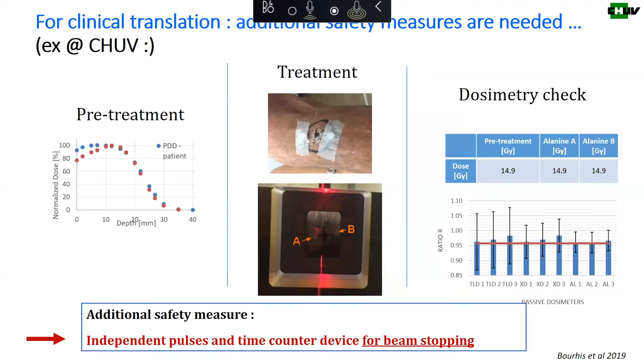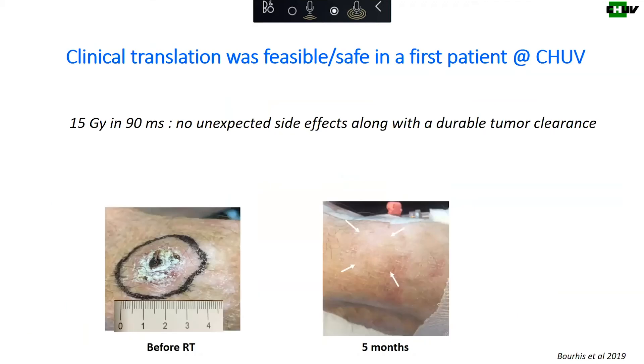For clinical translation, there may be additional safety measures needed, because it goes so fast that you want to stop the beam exactly after the number of pulses you need. In addition to a normal linac, we probably need an independent pulse and time counter device for beam stopping. We've used that in one patient so far — it proved feasible and safe, giving 15 gray in one fraction in 90 milliseconds. We didn't get any unexpected side effects and the tumor durably disappeared.